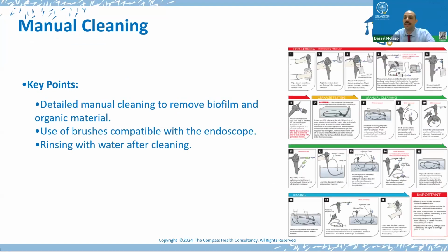So what about manual cleaning? It is an essential practice before the automated or manual disinfection. It is the most important step in removing the microbial bioburden from the endoscope, because failing to do that will cause failures in disinfection or sterilization. So IFUs should be followed. The proper time frame for reprocessing must also be respected. If there is a delay in reprocessing, you also need to apply the IFUs.